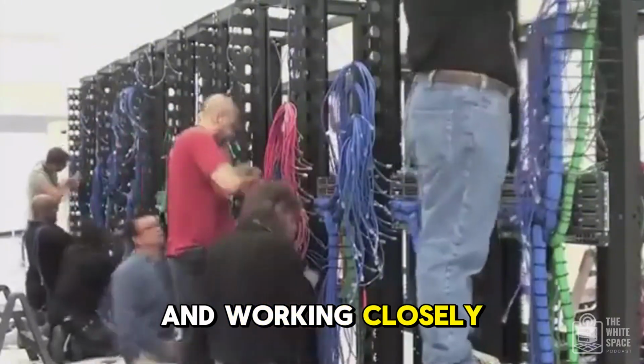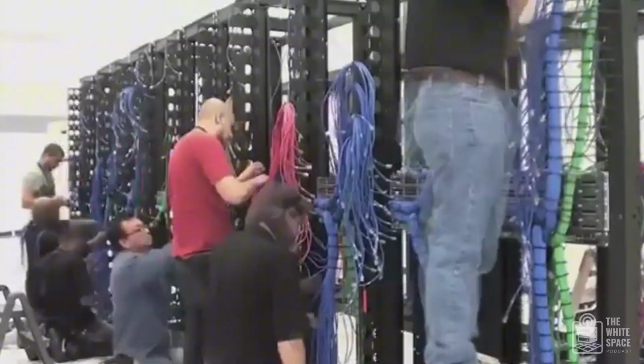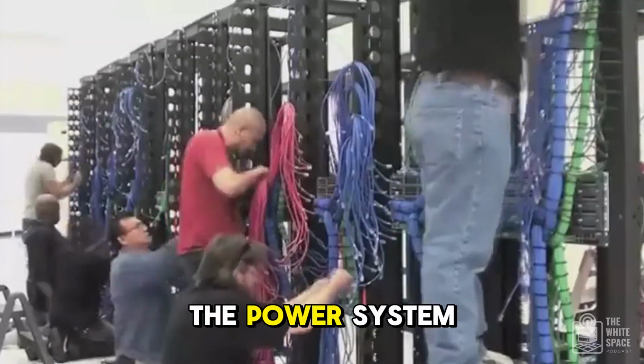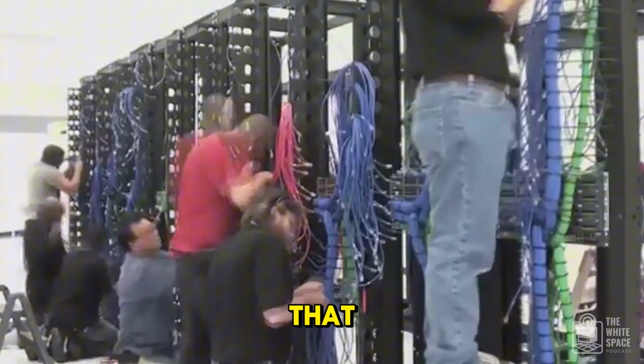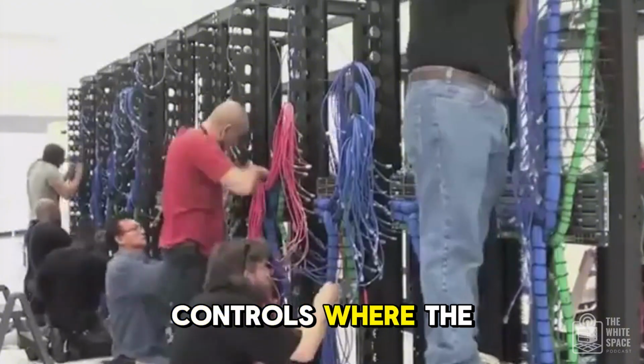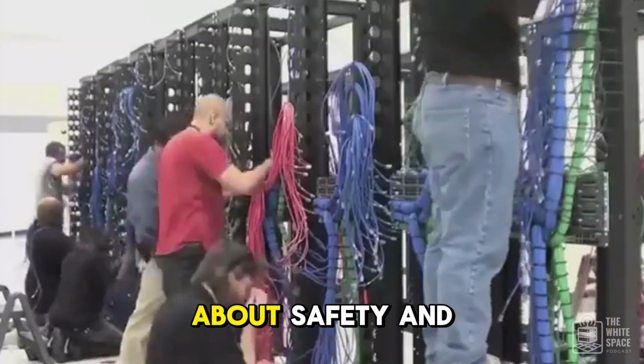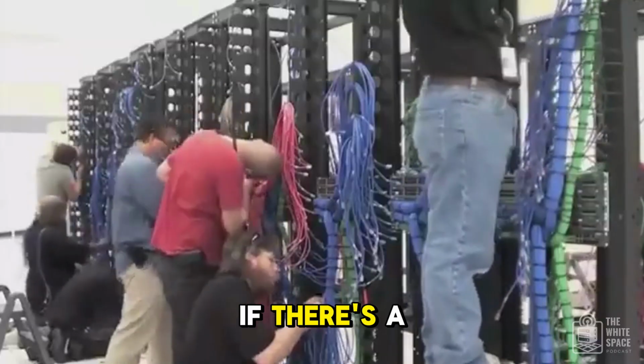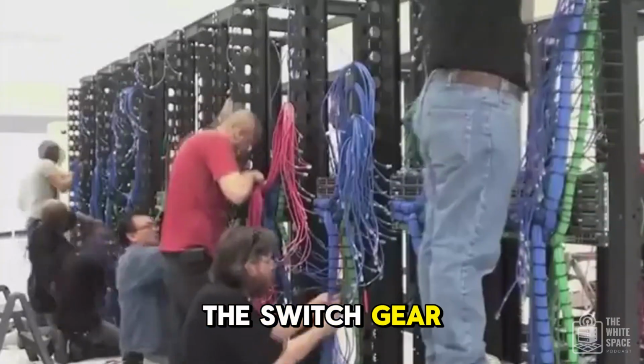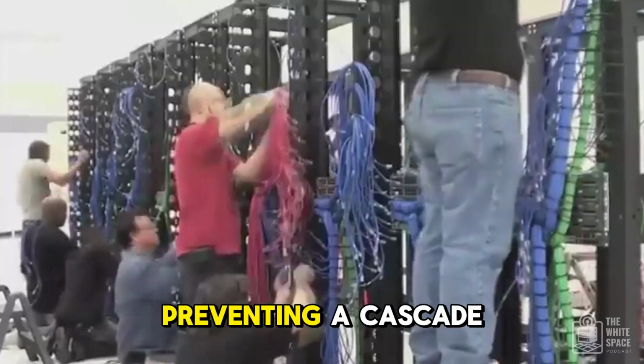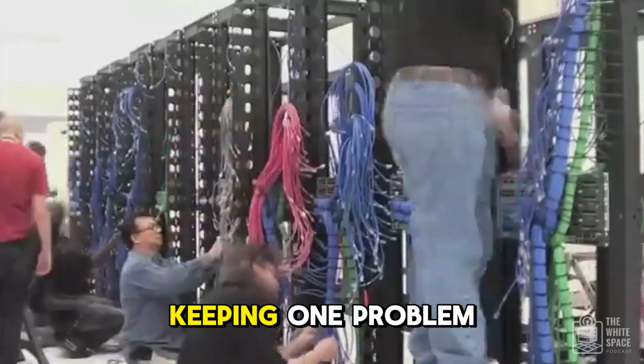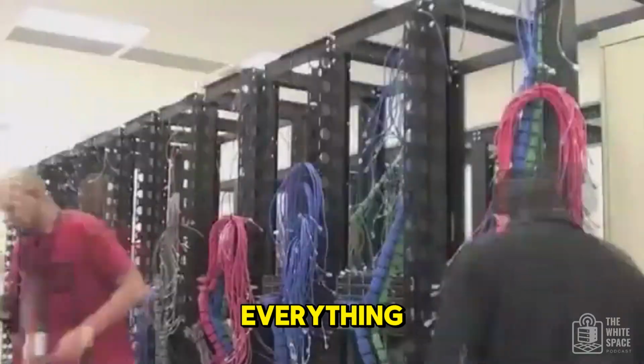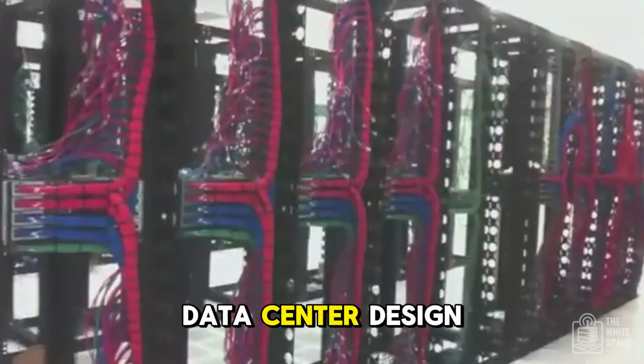And working closely with that, you have switchgear—I like to call it the traffic cop of the power system. It controls where the power goes, but crucially, it's about safety and isolation. If there's a fault somewhere, the switchgear can isolate that section, preventing a cascade failure, keeping one problem from taking down everything. That's fundamental data center design.